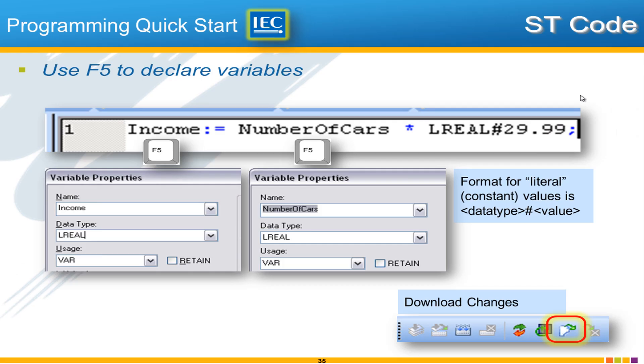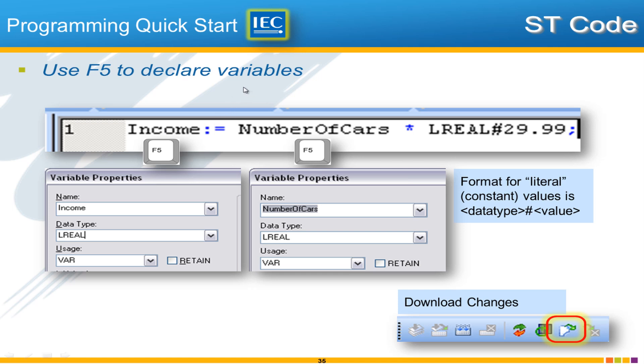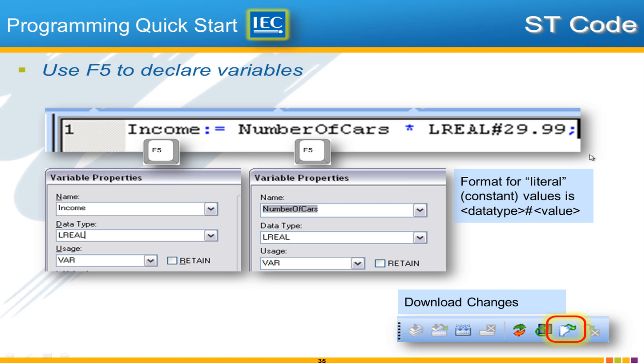So programming in the structured text language involves much use of the F5 key because the F5 key is used to declare variables and put those variables into the variable list of the POU. It's really important to use F5 and not just type in the word that you want for the variable. So let's go through it here. We'll hit F5, choose income. You can refer to this page of the training guide. We'll use data type LREAL in this case so that we can handle decimal places. REAL or LREAL would work, we'll use LREAL. We have income colon equals number of cars times LREAL pound 29.99. This is the format for the literal data, a constant.